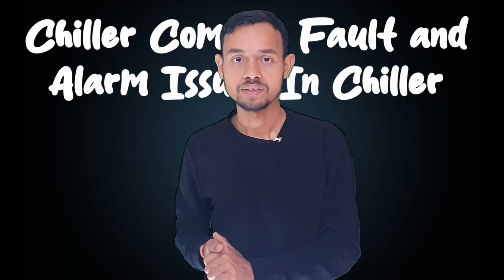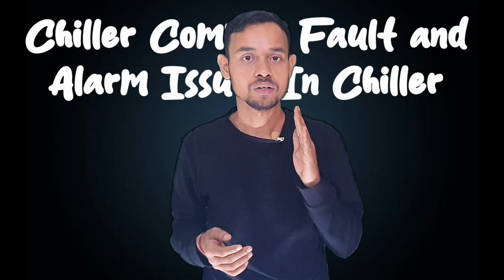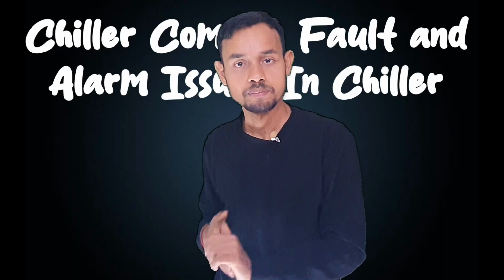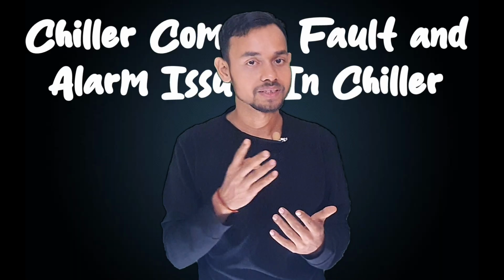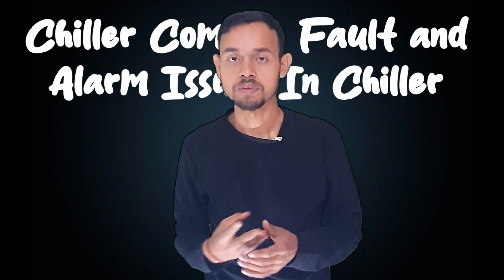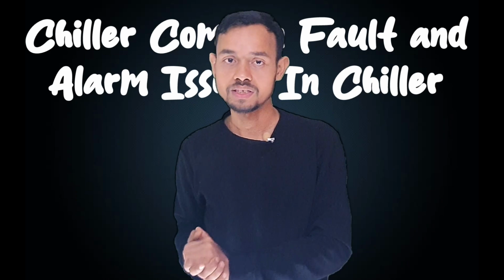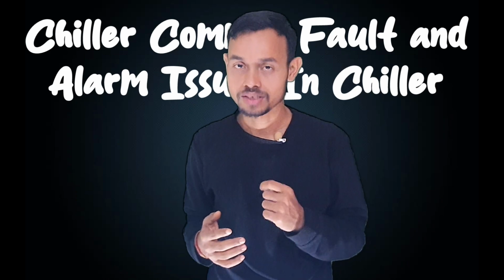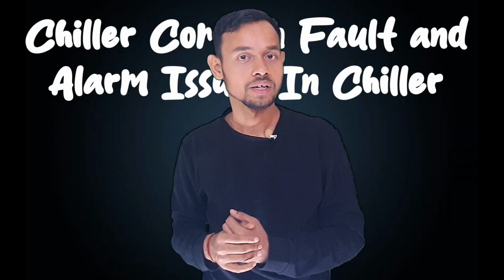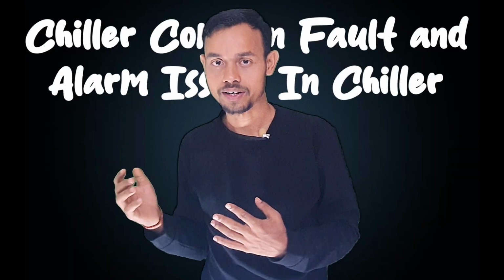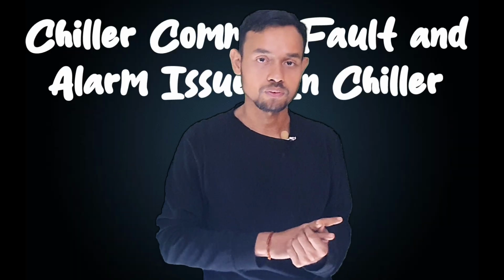Problem number 7 is refrigerant high or low temperature alarm. Let's see the cause of this problem. First is incorrect refrigerant charge, expansion valve issue, and improper water flow rates. Let's see the solution of these problems.